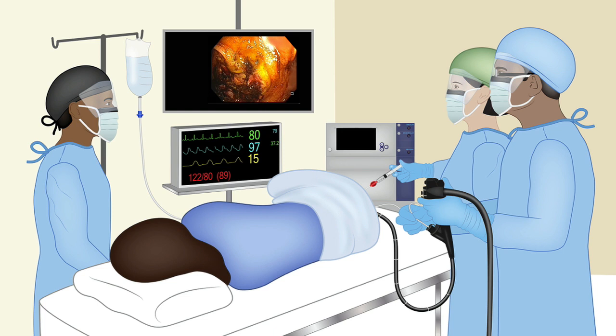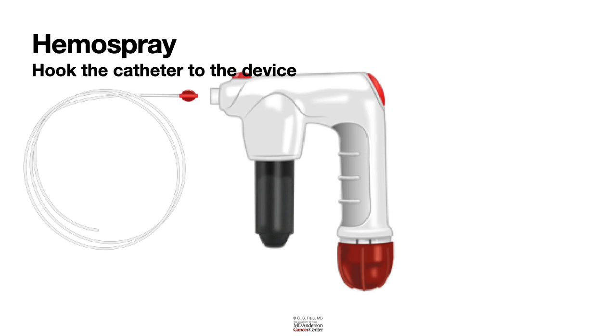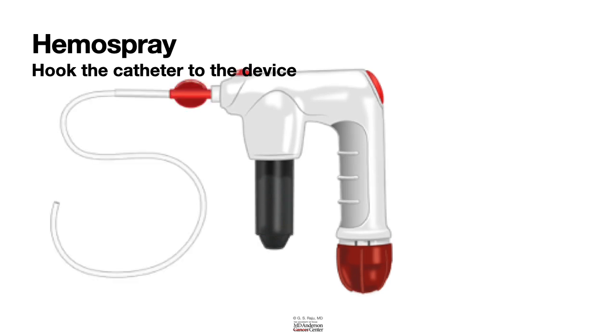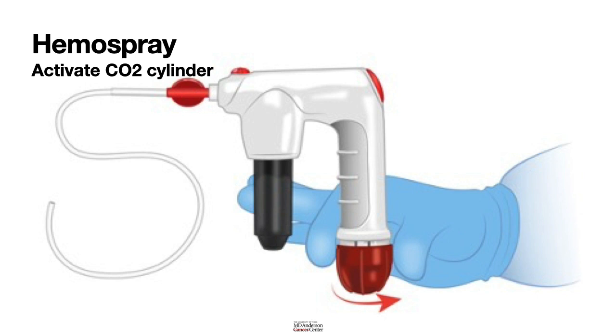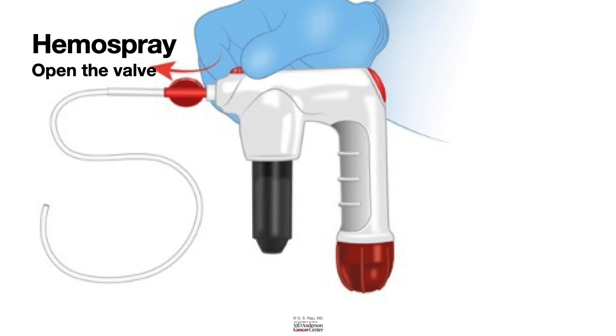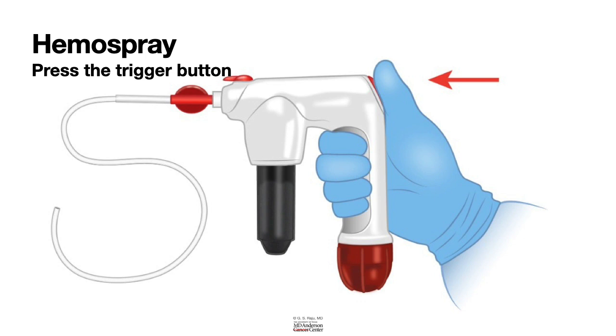And once the catheter has gone down, you hook the catheter to the device tightly, and then you activate the carbon dioxide cylinder by turning the red knob in a clockwise direction till it stops. Then you open that red valve by turning it in the direction of the catheter, and once it's there and the endoscopist suggests that you start, you press on that red button, that's a trigger button, for 1 to 2 seconds. That will give you a pulse of CO2 and drives the Hemospray powder down the catheter channel onto the lesion.